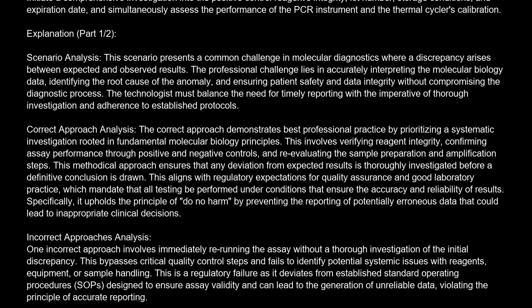Specifically, it upholds the principle of do no harm by preventing the reporting of potentially erroneous data that could lead to inappropriate clinical decisions. Incorrect approaches analysis. One incorrect approach involves immediately rerunning the assay without a thorough investigation of the initial discrepancy. This bypasses critical quality control steps and fails to identify potential systemic issues with reagents, equipment, or sample handling. This is a regulatory failure as it deviates from established standard operating procedures, SOP, designed to ensure assay validity, and can lead to the generation of unreliable data, violating the principle of accurate reporting.